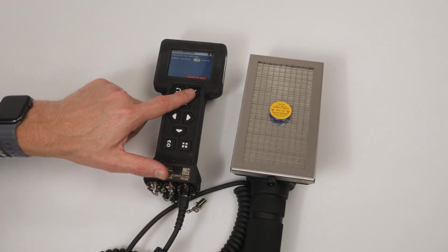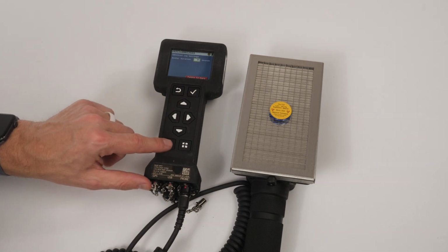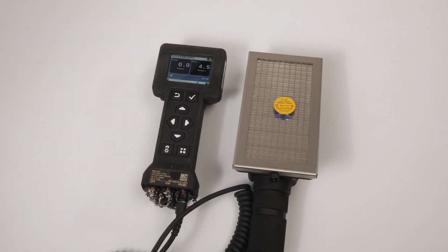Press the Home power key to return to the home screen. Press the left arrow key to start the scalar count and continue to hold the check source in place for the duration of the scalar reading, which is a countdown of the 30-second duration. Note the number of counts reported in the beta radiation reading panel at the end of the 30-second count.